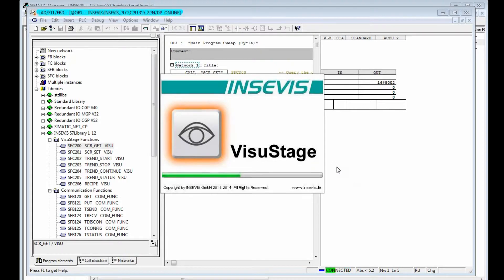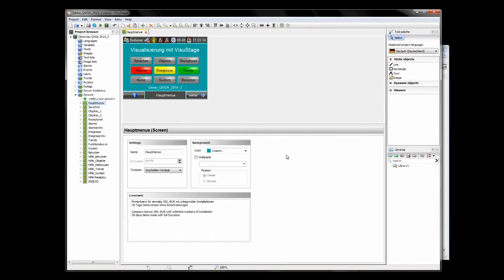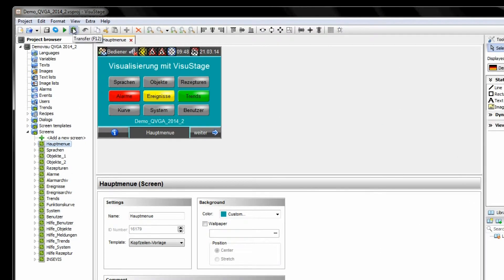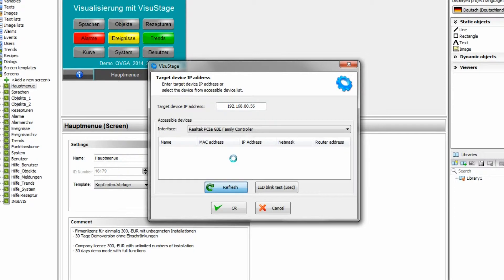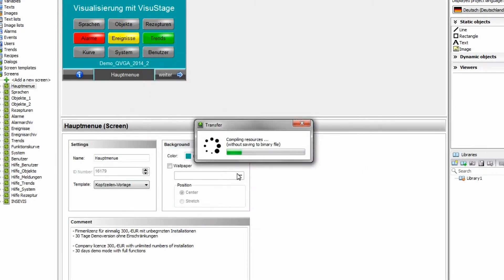Of course, we have to download the visualization with all its languages and screens, here the whole sample project into the panel PLC as well if we want to control it. Therefore, we identify all accessible nodes, select our device by its IP address. The VisuStage compiles the visualization into a binary file and then it downloads this binary file into the selected PLC.